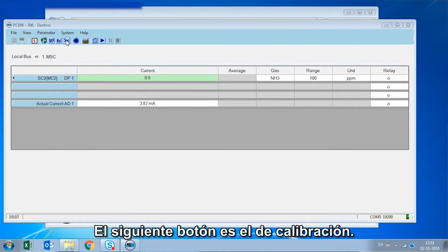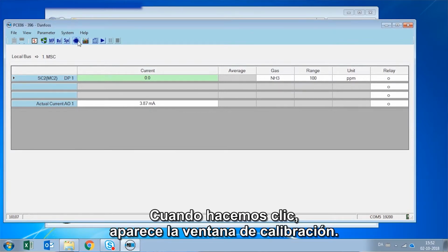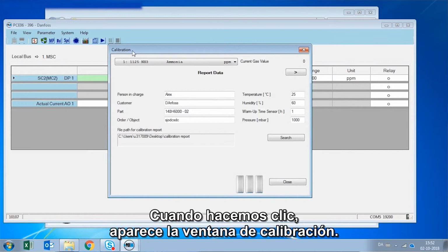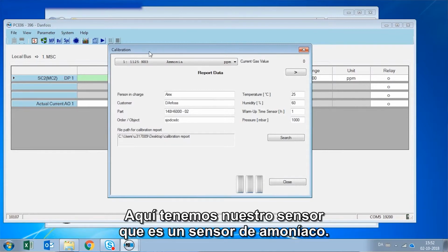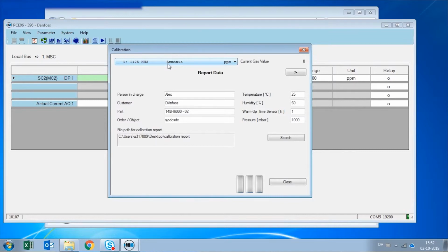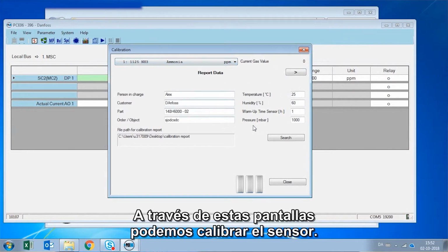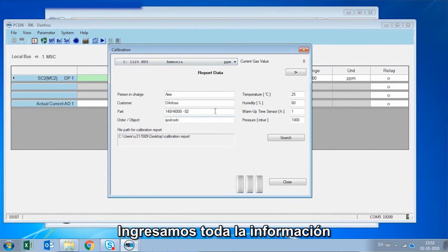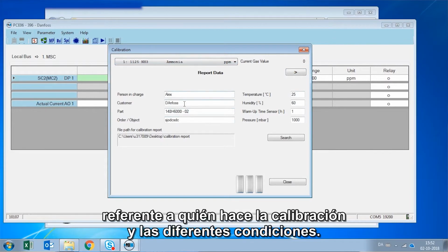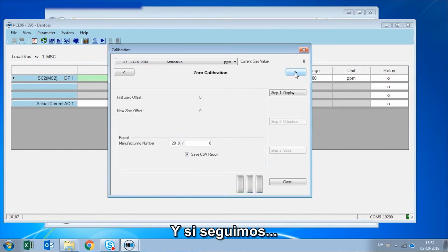On the next button, you can see that it's called calibration. So when we click on this one, a calibration window pops up. And here we have our sensor, which is an ammonia sensor. And through these screens, we can calibrate the sensor. We are going to enter all the different information in regards to who is doing the calibration and the different conditions.